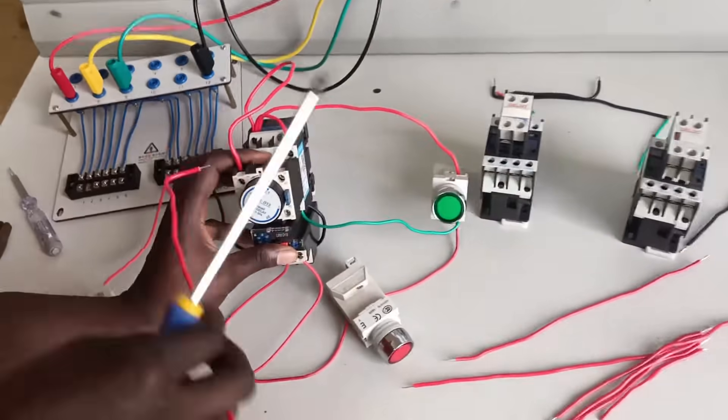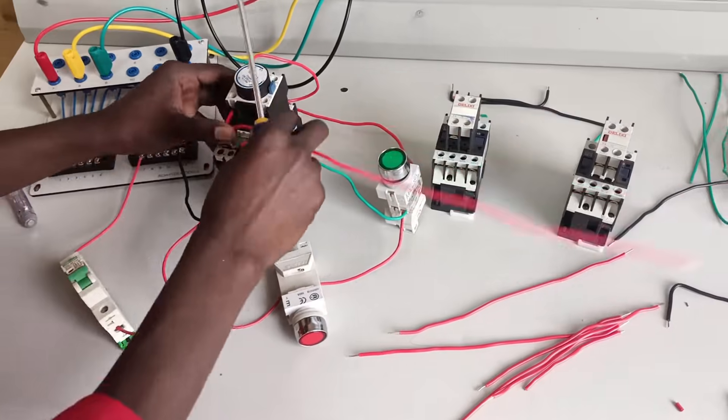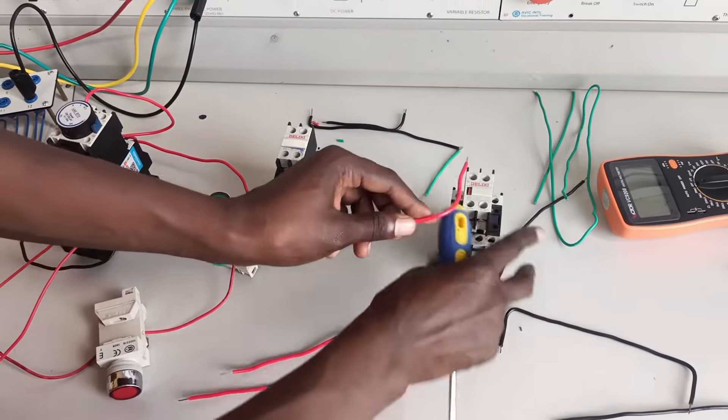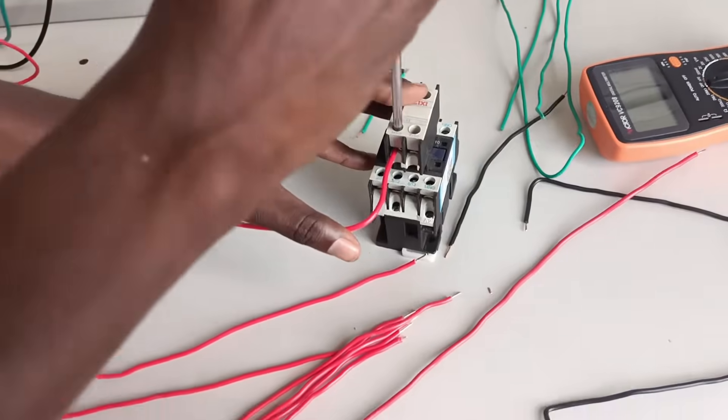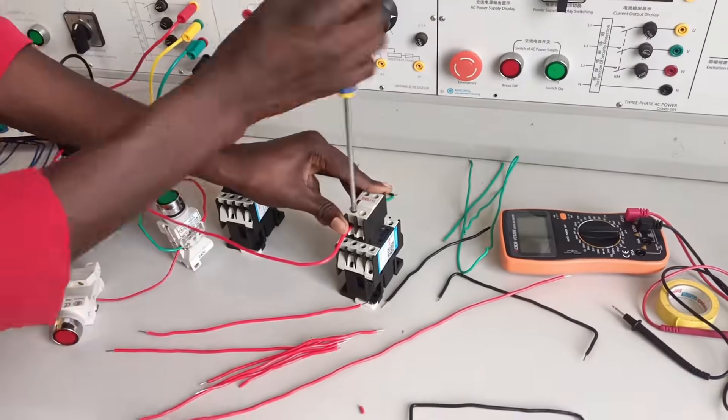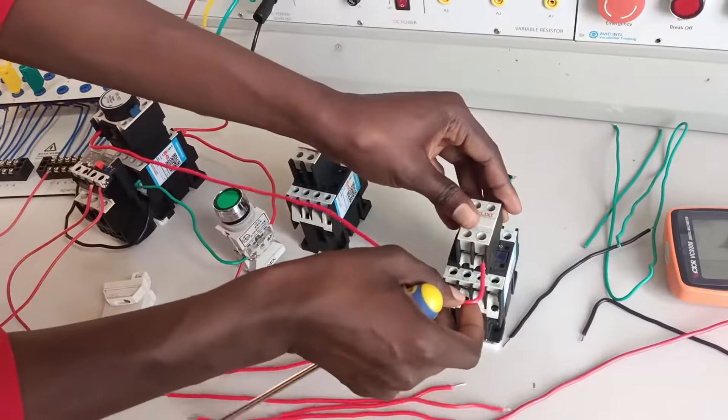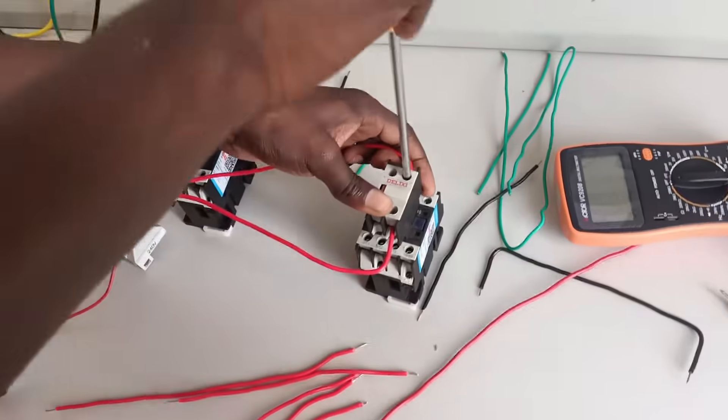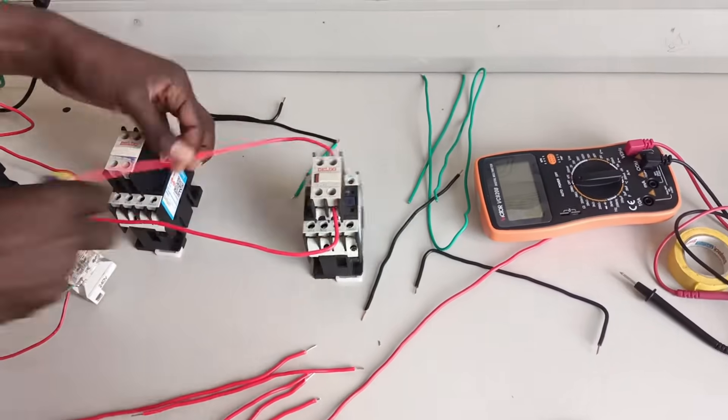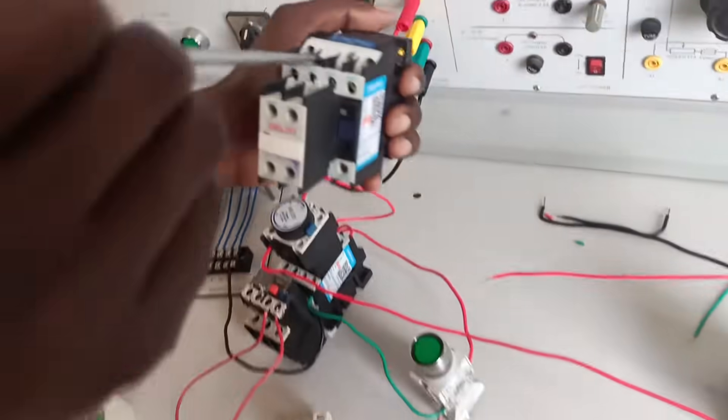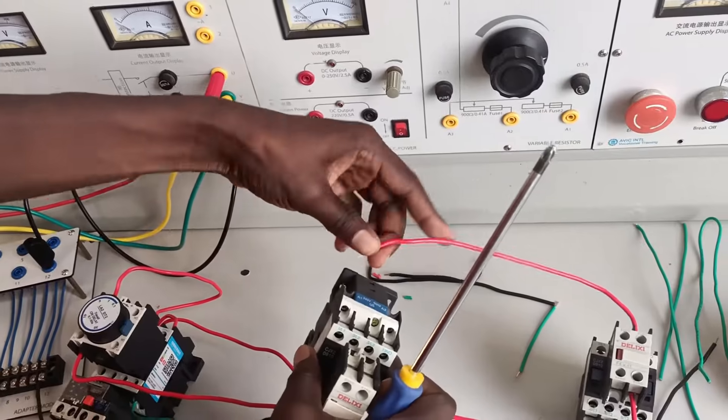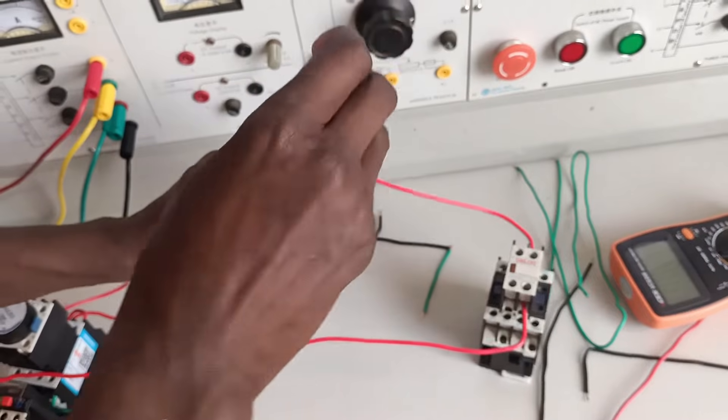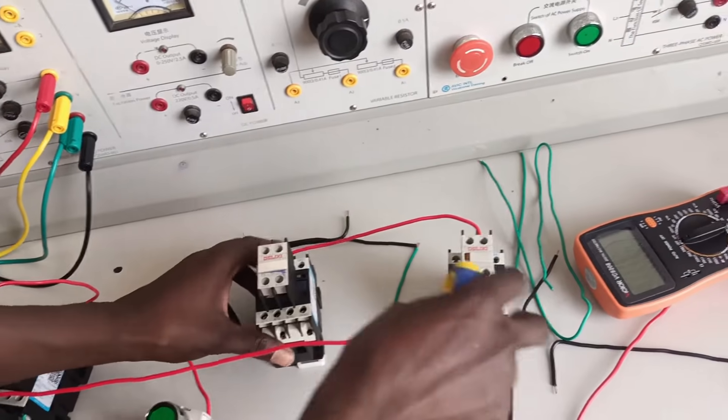Now let's do it for the timer and the remaining contactors. From the normally closed of the timer we are going to take it to the delta energizing coil, but through the normally closed terminals of the star contactor. That one we call interlocking connection. I'll tell you why we do that. From pin 22 of the star, we'll go to the A1 of the delta contactor. That's contactor 2, for the delta.